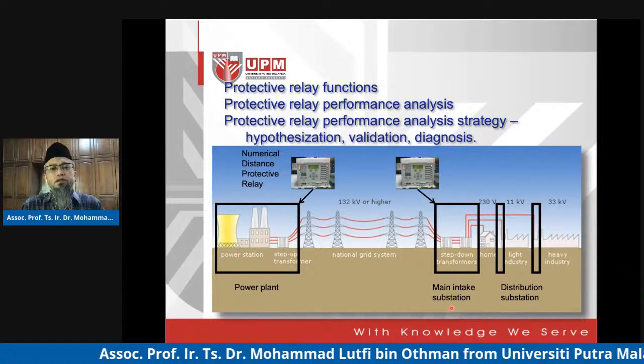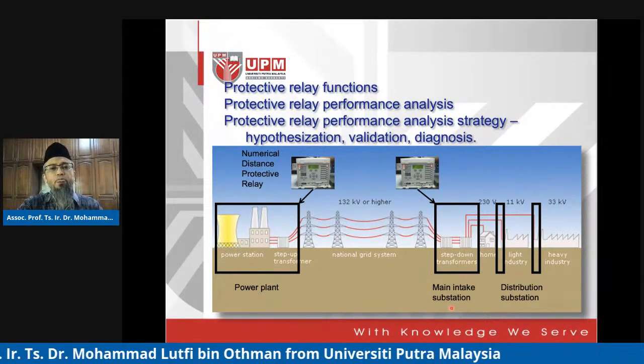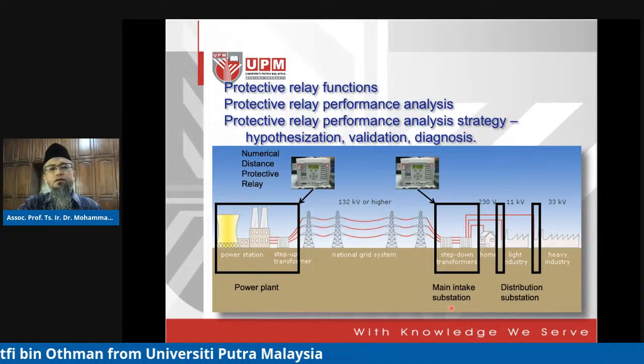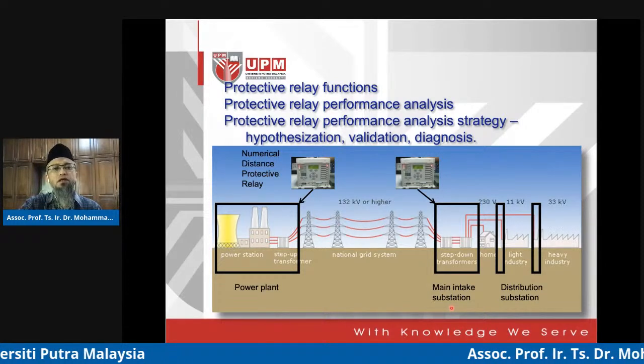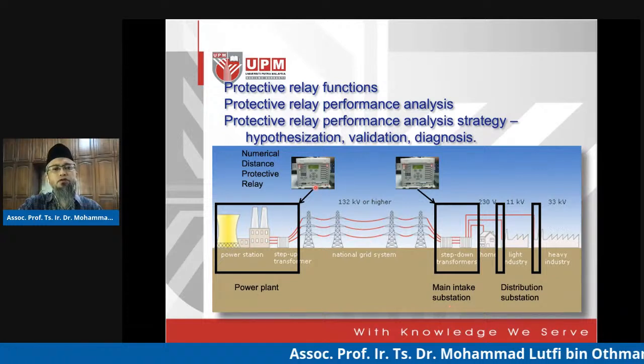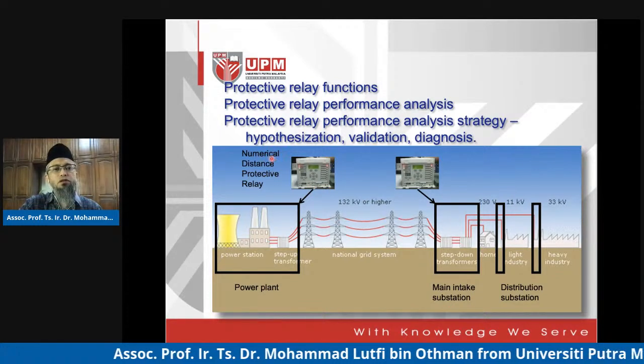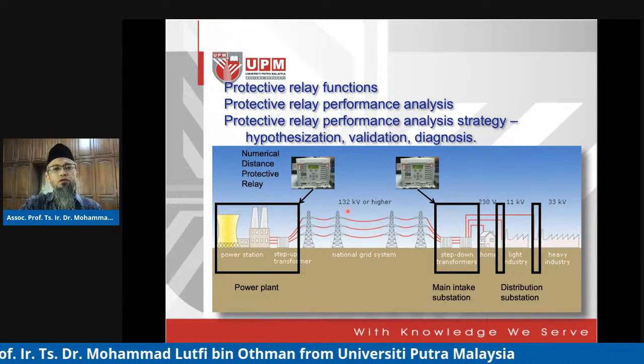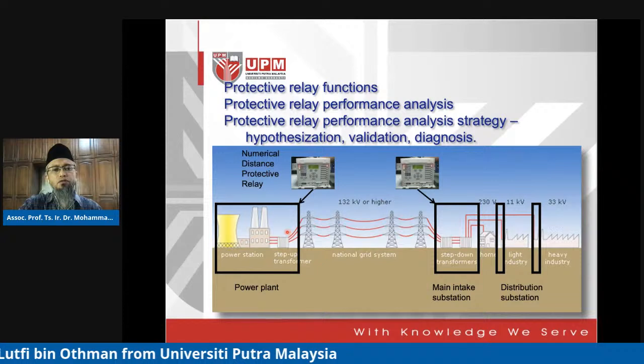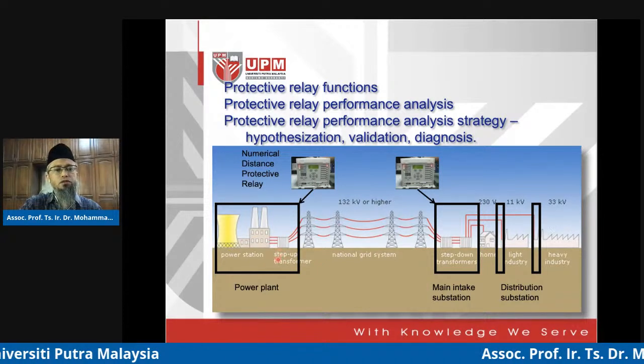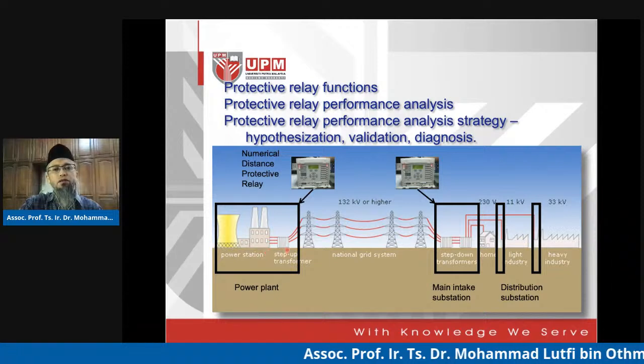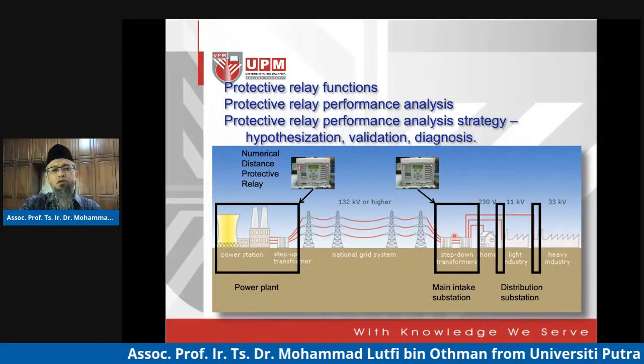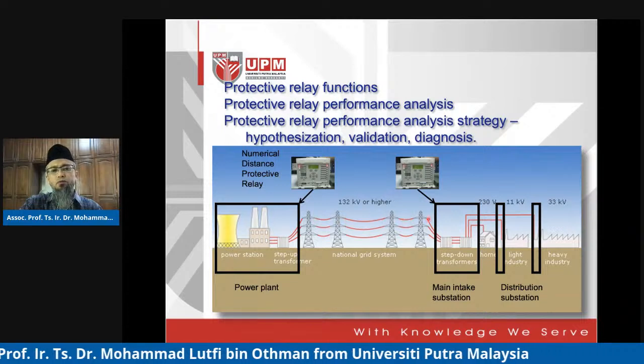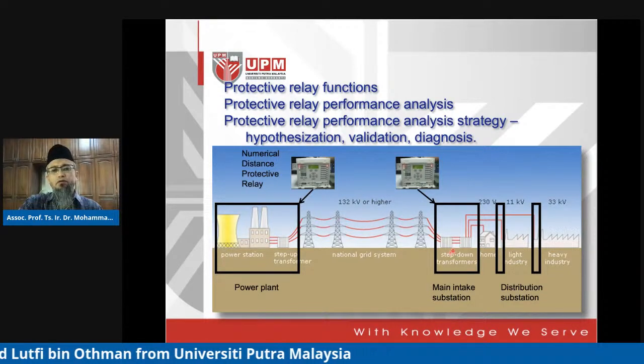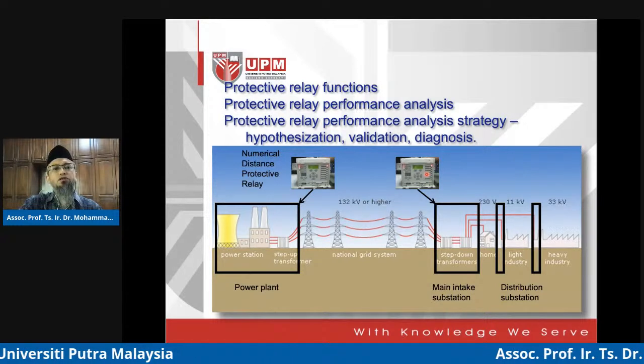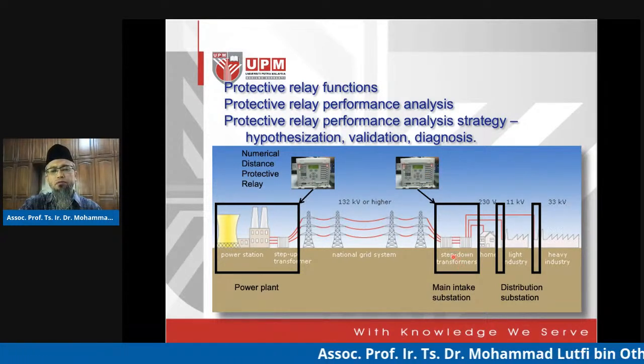Related to power system protection, if you locate some of these IEDs, intelligent electronic devices—for example, one very familiar for transmission line protection, the numerical distance protective relay—we would normally locate one at one end of the line, in one substation, shown here as located near the power plant. And we have another right at the very end of the transmission line, possibly hundreds of kilometers away, far from the first one. We have another similar distance protective relay located at another substation.